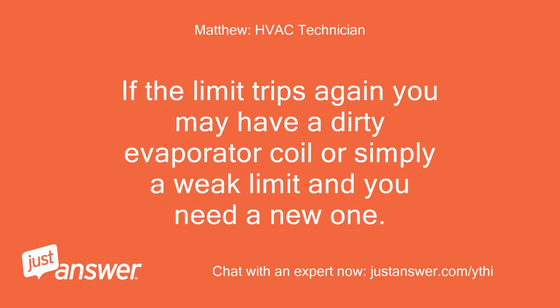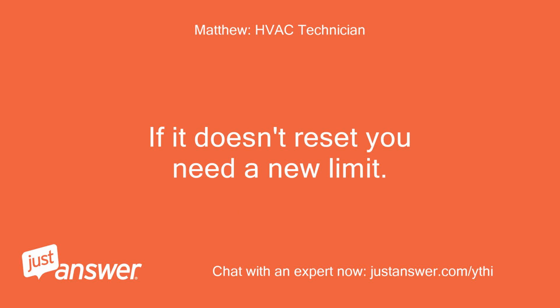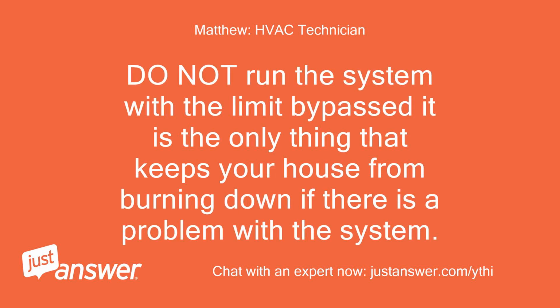If the limit trips again, you may have a dirty evaporator coil or simply a weak limit and you need a new one. If it doesn't reset, you need a new limit. Do not run the system with the limit bypassed. It is the only thing that keeps your house from burning down if there is a problem with the system.